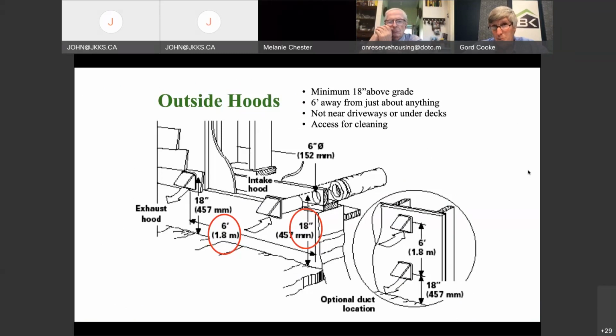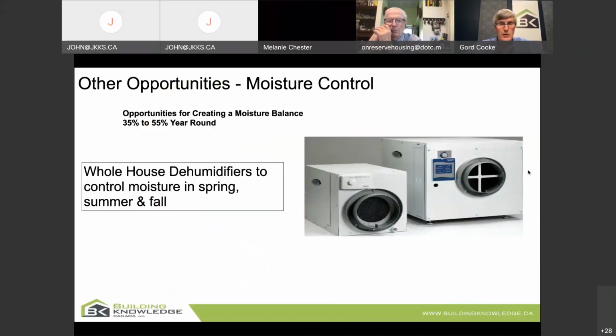I definitely want to make sure that wherever I'm pulling fresh air in, it's indeed fresh air. I don't want it next to an exhaust outlet from the dryer, for example. There's an example - you don't want it pulling behind the barbecue, you'd want it up above. The fresh air intake is actually on the right-hand side there, up off the ground a little bit. On the left-hand side you have the exhaust from the dryer and the exhaust from the HRV in the same location.